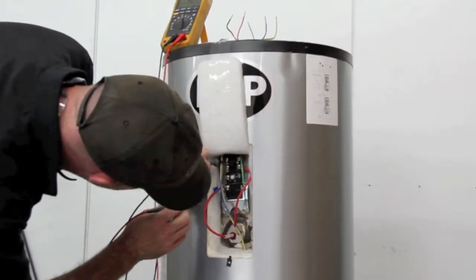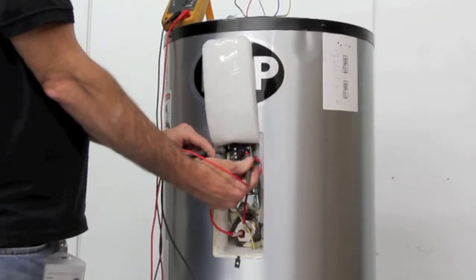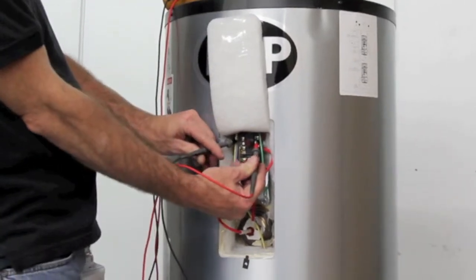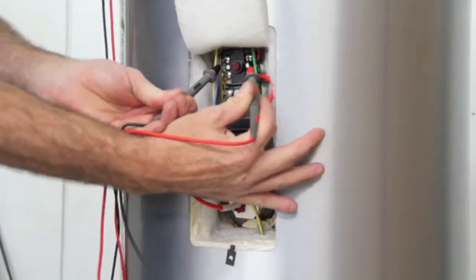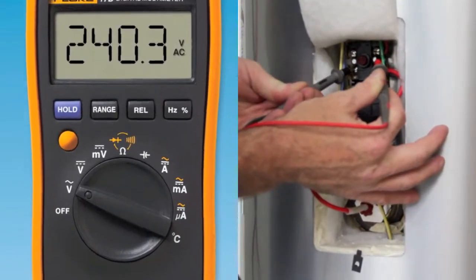Using a multimeter, verify supply power to upper thermostat high limit control terminals 1 and 3. In our example, 240 volts AC should be measured across terminals 1 and 3. If no power is measured, refer to the supply power section.